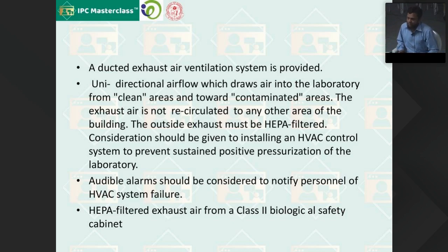For the BSL3 lab, please keep in mind you need to have a biosafety cabinet type 2A or type 2B. Okay, and the second thing to keep in mind is the unidirectional flow of air, and the exhaust air has to be HEPA filtered. And whenever you are doing any aerosol generating procedures, you need to have a heating ventilation HVAC control system to avoid infections. An audible alarm should be considered to notify the personnel of HVAC system failure, and HEPA filtered exhaust air from the class 2 biological safety cabinet.